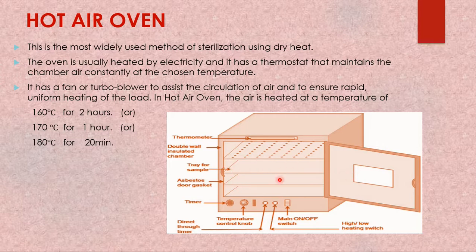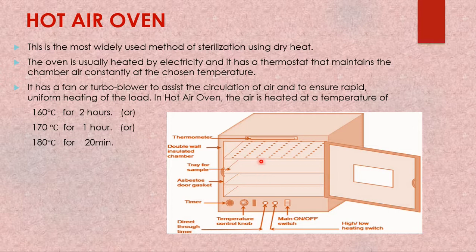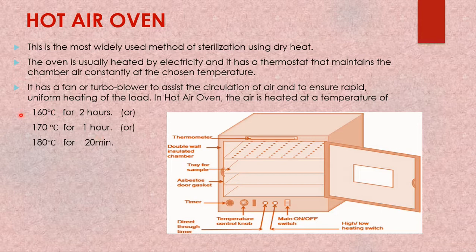Once articles are placed inside and the door is closed, you control the temperature. The sterilization temperatures for a hot air oven are: 160°C for 2 hours, 170°C for 1 hour, or 180°C for 20 minutes. The electricity heats the elements, generating heat that warms the air, and the fan circulates it around all the articles.